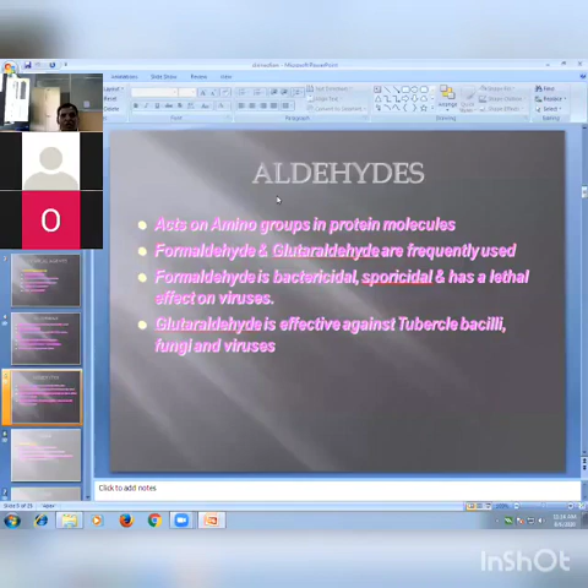Then the use: formaldehyde is used to preserve the anatomical specimen, destroying anthrax spores in hair and wounds. 10% formalin plus 0.5% sodium tetraborate is used to sterilize metal instruments. And glutaraldehyde is used to treat corrugated rubber anesthetic tube, face mask, plastic endotracheal tube, metal instrument, and polythene tubing, and for sterilization of cystoscope, bronchoscope, and endoscope. For all these scopes, this glutaraldehyde is used.